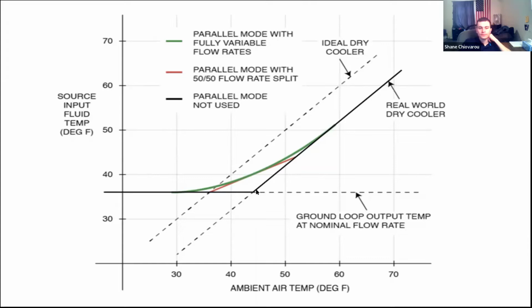Oh, okay. So anyway, if you have just an air source heat pump, then you're going to be along this line right here. So if you're trying to heat your building, okay, well, I should explain. Source fluid temperature, this is what's coming into the heat pump. Ambient air temperature, that's what the air temperature is outside. So basically right here is the freezing point for the ambient air, 32 degrees Fahrenheit. So now you'd be coming down here where most of us live. We can get down to pretty much zero or even below. So that's way down here.